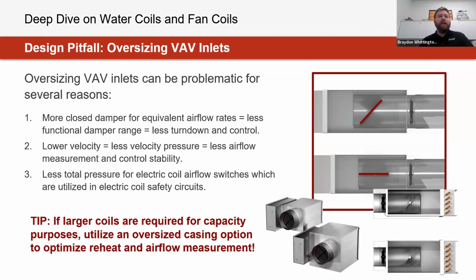This also highlights that utilizing oversized casings can be effective for both optimizing reheat and airflow measurement. The reason is that you might have lower minimums for your valve size, so being able to bump up the casing size but keep the same valve size can be an effective solution when looking at lower water coil performance for a VAV.